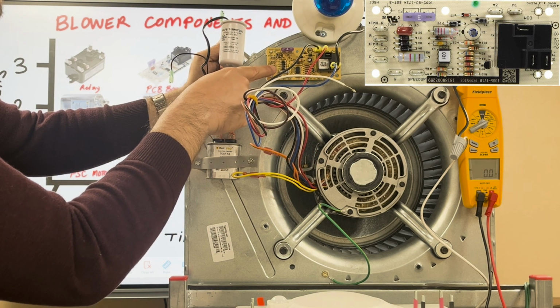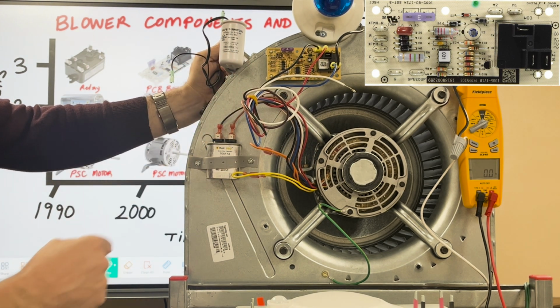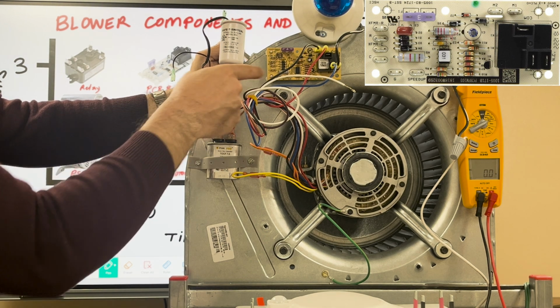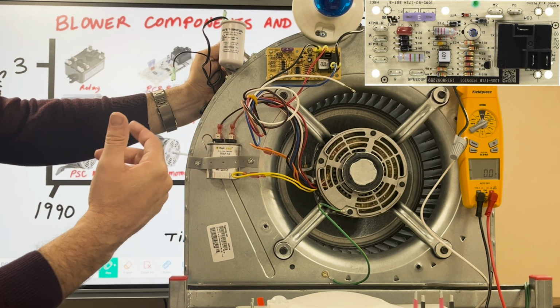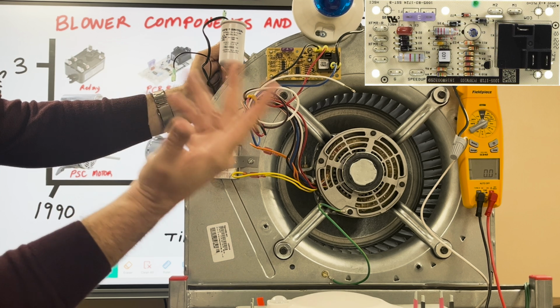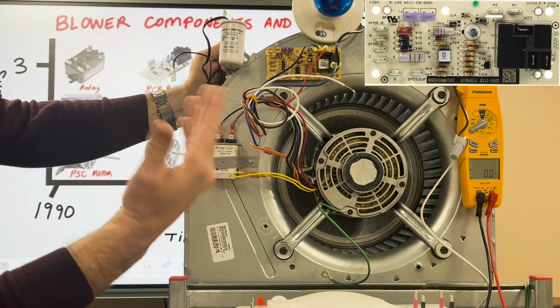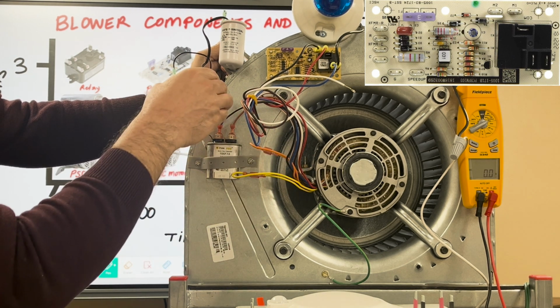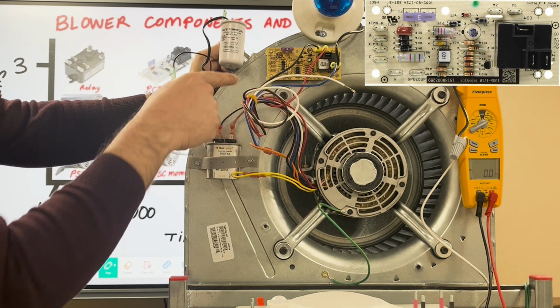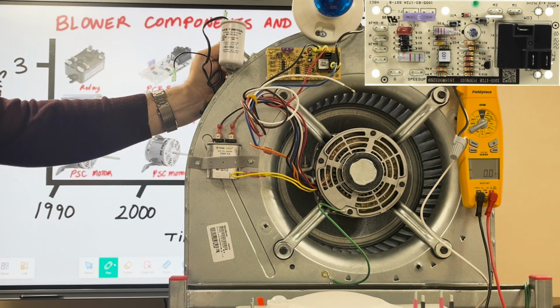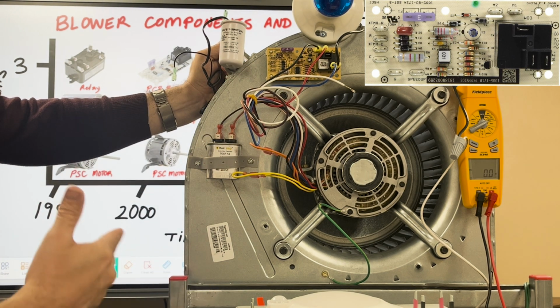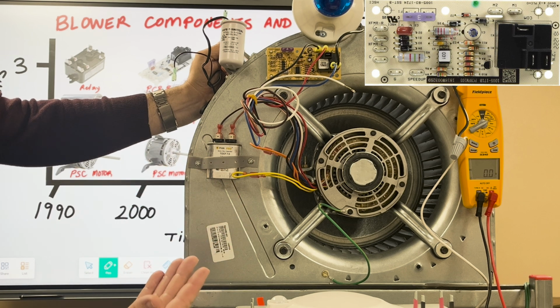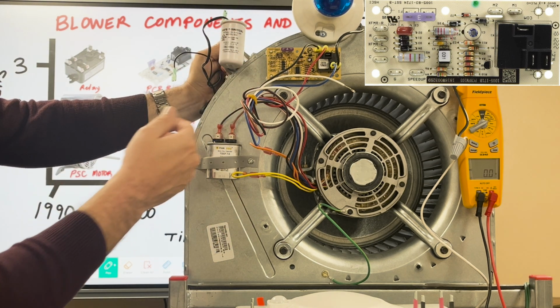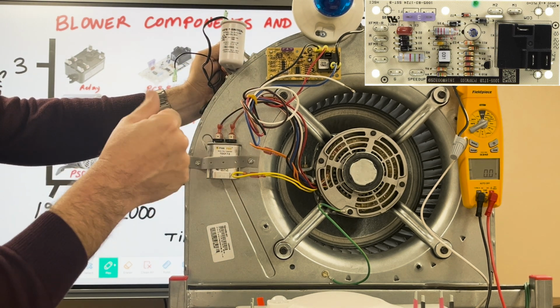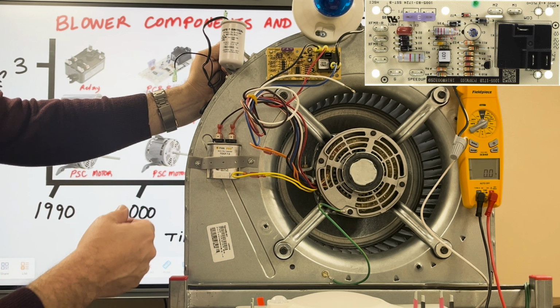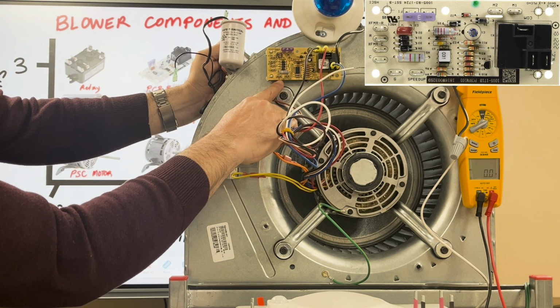And then I have another common. If I wanted to use that, say I'm running to my thermostat, or if I need a common for my heater relay for my heat strips, I would wire that to here. They're just trying to give you enough terminals so you don't sit there using a bunch of wire nuts. It's easier to diagnose things if you can get your leads in there versus taking a bunch of wire nuts off. Down here we have G.